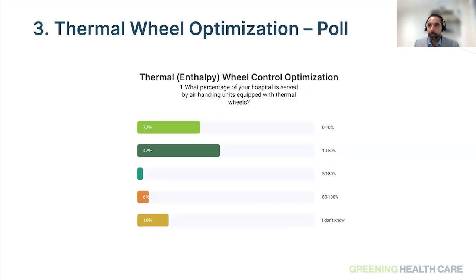While Michael shares the third poll about the thermal wheels, I can share the results of the second poll. Around 26% of the hospitals still have perimeter systems on in summer. That would be a good measure for them to review with their team. There's 21% that are currently working through knowing their answers, and 12% have some perimeter heating systems open. So that measure on its own is very simple: turn off those perimeter pumps in these facilities, so you could save not only on the heating but also on the chilled water.